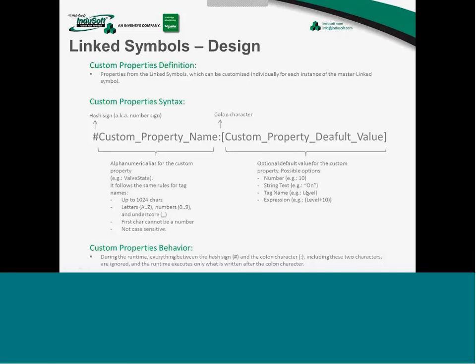Could be a tag name, so it's dynamic. The value of the property will be the value of that tag. Or it can be an expression between parentheses. So let's see how, and by the way, the behavior during the runtime for the custom properties is that during the runtime, InduSoft ignores everything between the hash sign and the colon, including the hash sign and the colon character. It executes only what you have after the colon character.